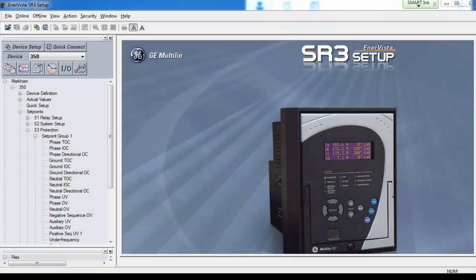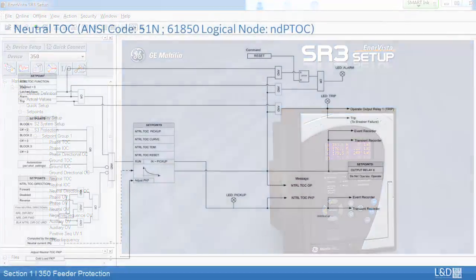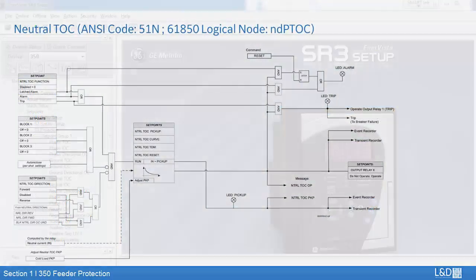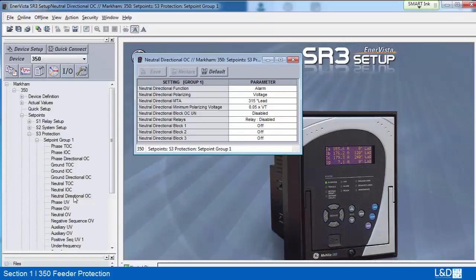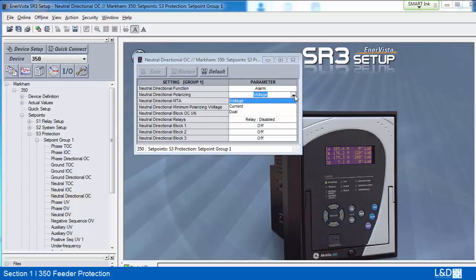In neutral TOC, the defined time delay is replaced with inverse time delay. Neutral directional element is used to discriminate fault direction for neutral IOC and TOC, and its configuration is more complex than phase directional. A polarizing signal for the neutral directional element can be set to either voltage, current, or dual.